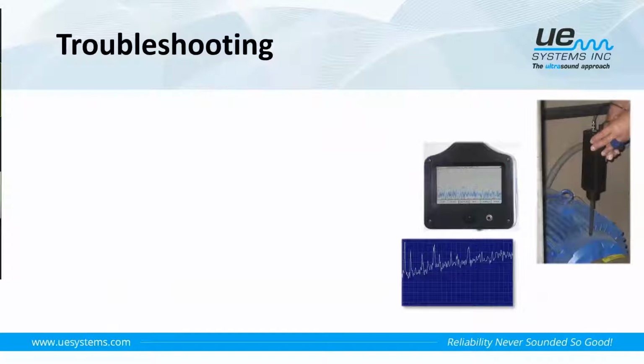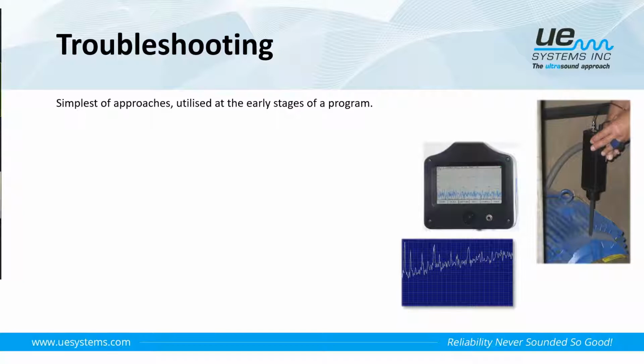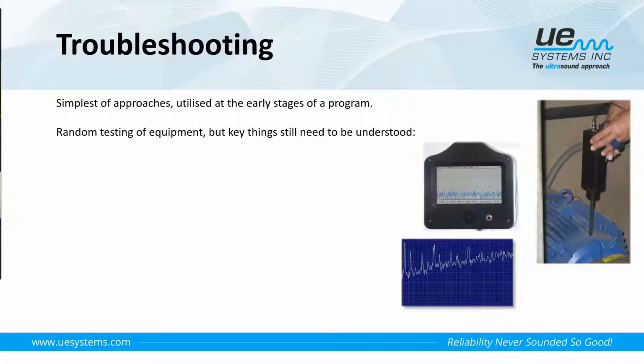So, the troubleshooting method. One of the simplest approaches utilized in the early stages of any sort of program, because we all have to start somewhere. And like you would when you walk through a plant and you're listening for sounds audibly, we're doing that with ultrasound, but at an earlier stage because of the high frequency. So we're going to be hopefully picking things up at an early stage. So this is where we're doing some random testing of equipment. You know, we're troubleshooting, we're popping in and out. Maybe somebody has told us that something doesn't quite sound right to them.